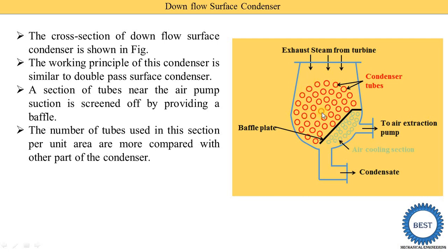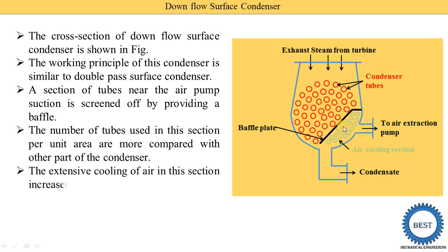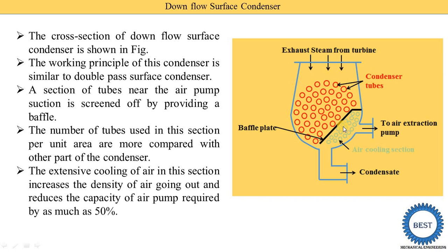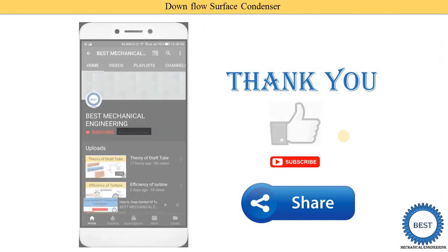Suppose in the main region one square meter has eight tubes, and a similar square in the air cooling section has 12 or 15 tubes — more tubes are provided here. The extensive cooling of air in this section increases the density of air. Due to this, we can reduce the capacity of the air pump required by as much as 50%.